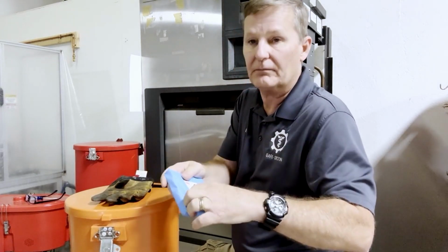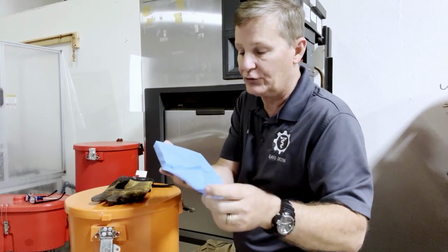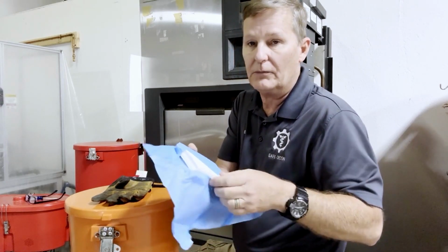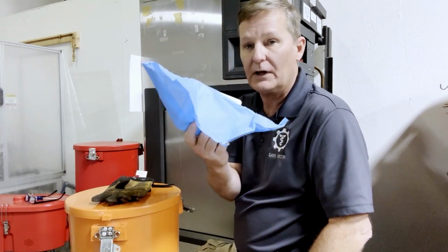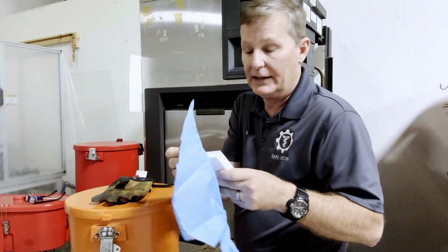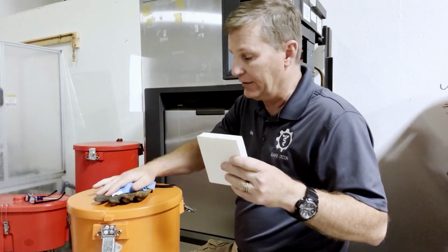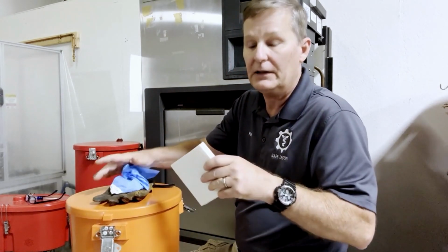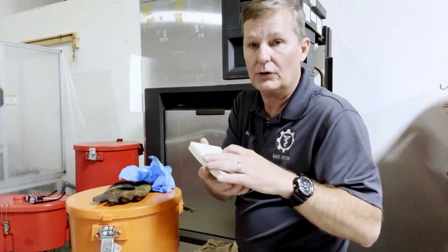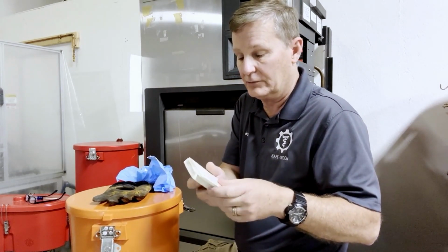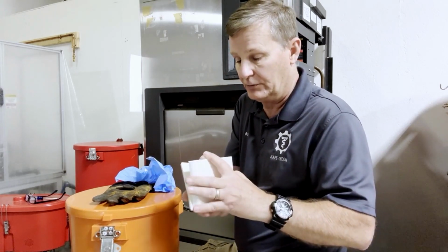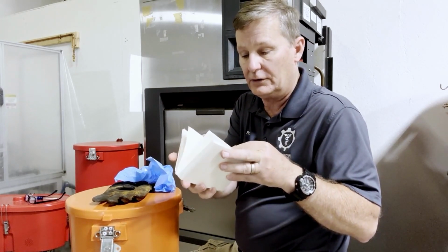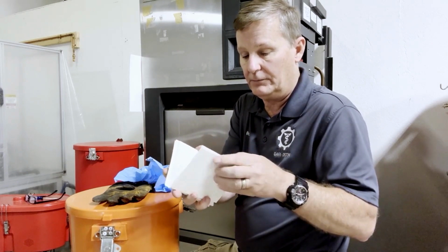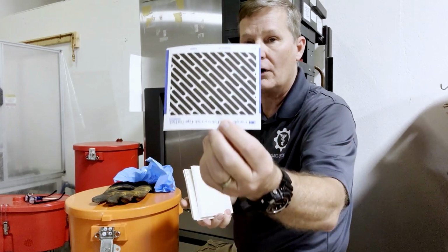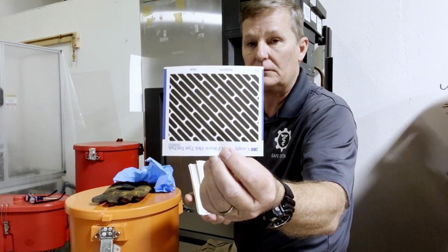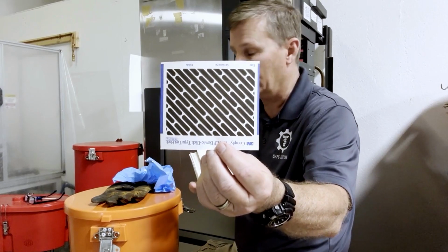So let's open it up, see what kind of steam penetration we were actually able to get. As most of you know, this test is difficult enough just for an autoclave to go through and achieve. But when you put it inside of an airtight container such as a Safe-Decon unit, to be able to get this to turn all black is going to be pretty impressive, I would think. And as we look, let's see here, and the question is where? There it is, and that's the steam penetration that we get in a Safe-Decon container.